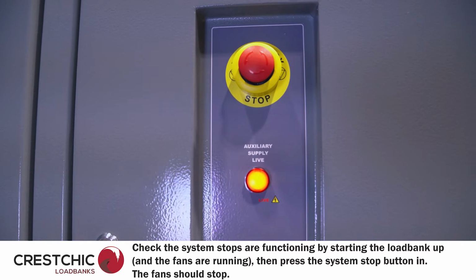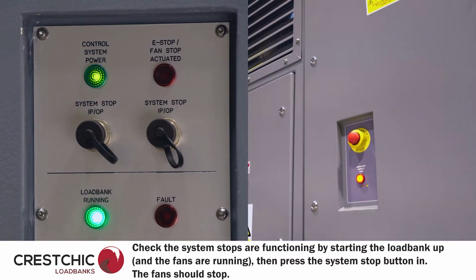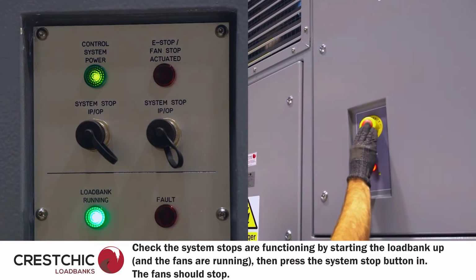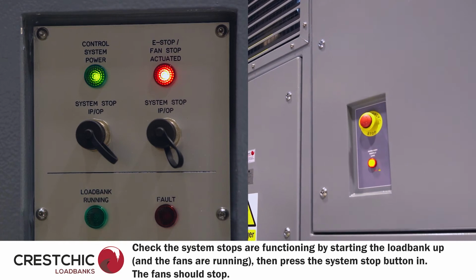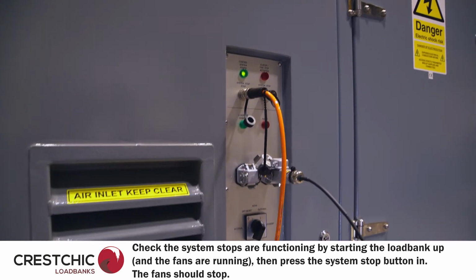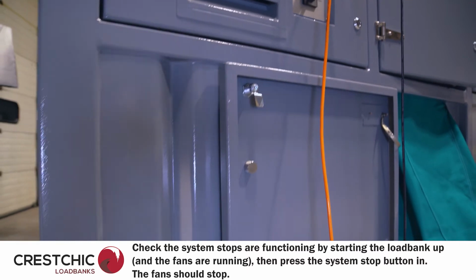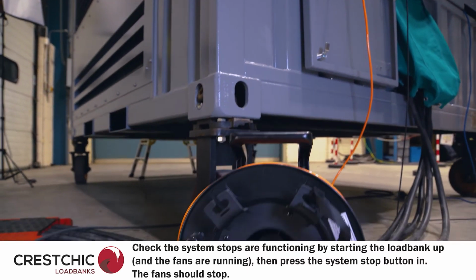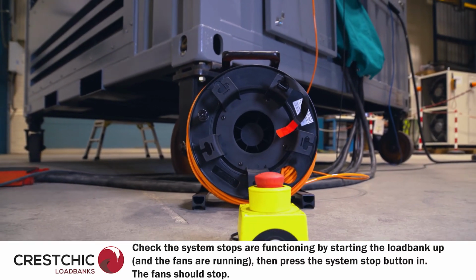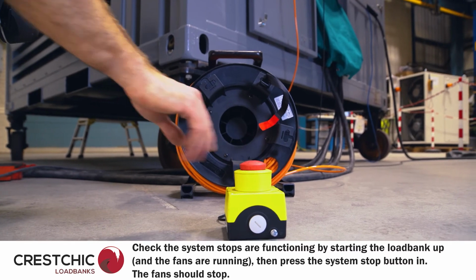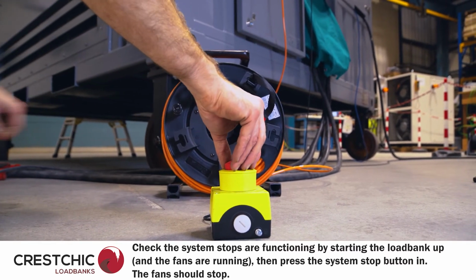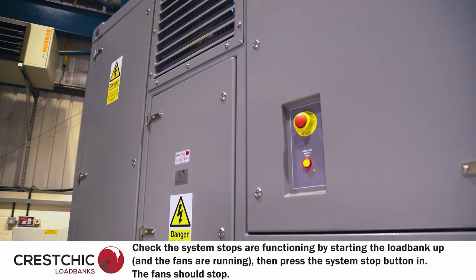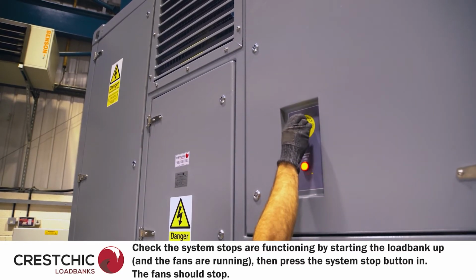Once the fans have been confirmed as functioning correctly, this is a good opportunity to test the system stop buttons. On pressing these, the fans will stop and communication with the load bank's controller will be lost. All load banks have a system stop button on their enclosure. It is also possible to connect a remote system stop button, and this should also be tested at this stage. Releasing the system stop button will restart the load bank and the startup sequence can be started again.